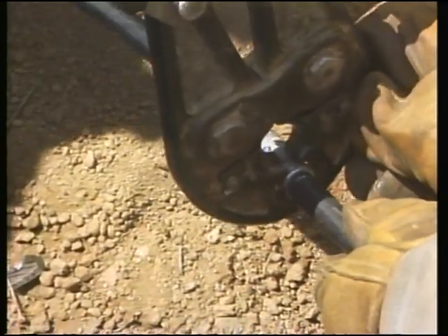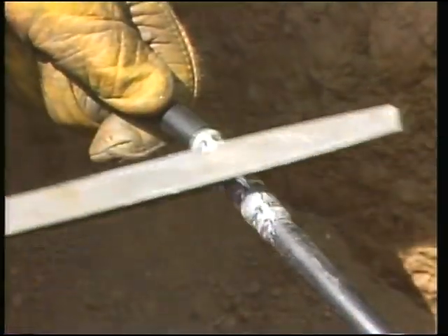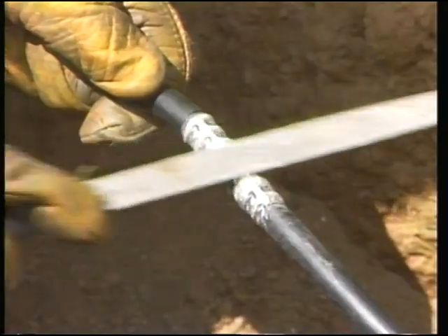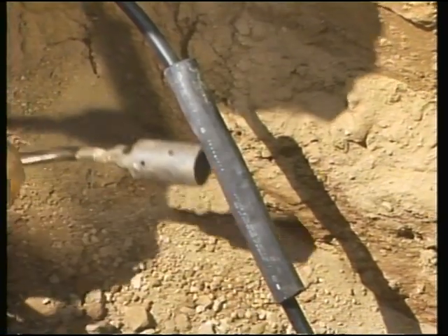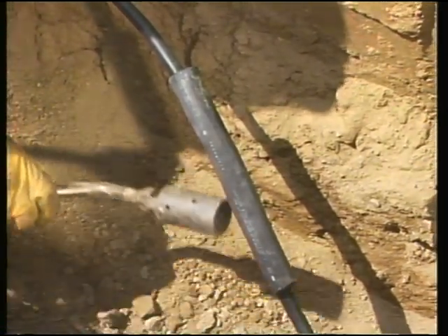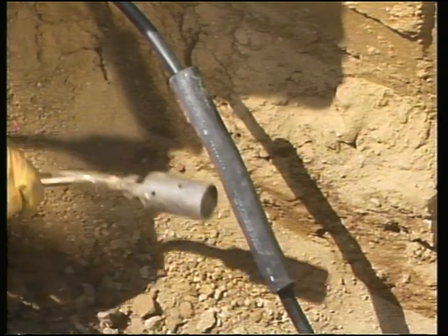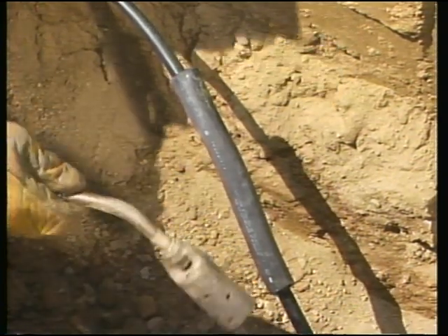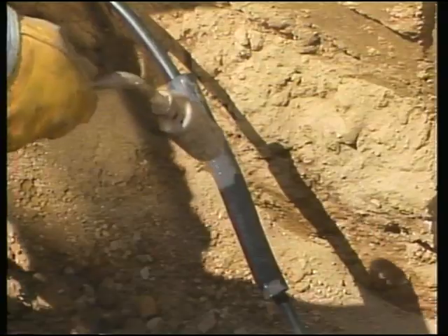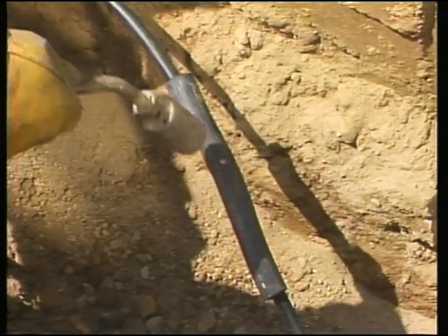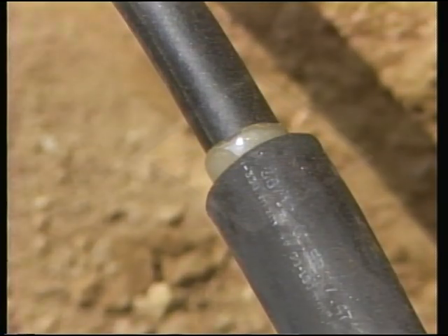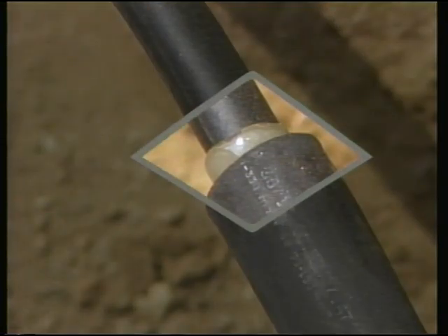After making the proper number of compressions on the connector, the workman smooths out any rough edges and cleans the splice. With the heat shrink tube centered over the conductor splice, the workman uses an approved heat source to shrink the tube over the splice using a brushing motion. The heating process continues until the tube is tightly adhered to the cable insulation and is smooth and wrinkle-free. As a further indication of when to stop, a white sealant will appear at each end of the tube.